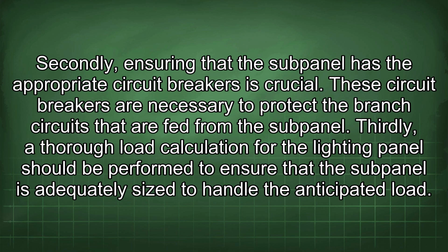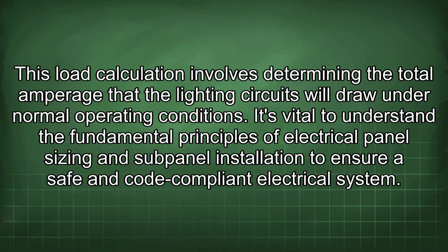Thirdly, a thorough load calculation for the lighting panel should be performed to ensure that the subpanel is adequately sized to handle the anticipated load. This load calculation involves determining the total amperage that the lighting circuits will draw under normal operating conditions.